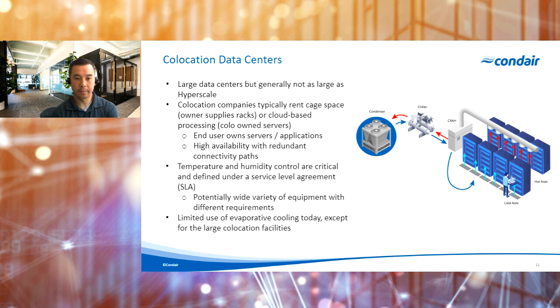So the co-location market tends to be a little bit different, as the operators are renting space. The space can be as small as a single rack, it could be a data hall, or even entire buildings can be rented to customers. In this type of facility, it's common for the co-location operator to manage the facility side of the building and maintain critical parameters such as temperature and humidity through service level agreements, while the individual or organization renting space manages the IT equipment.